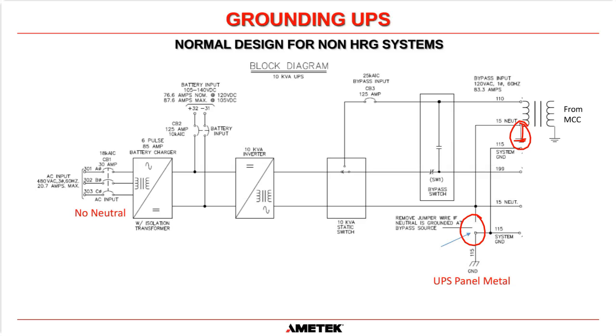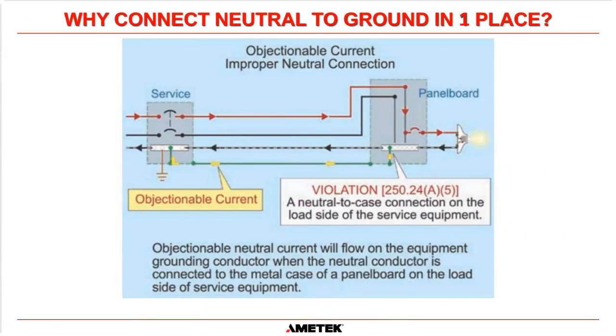Okay, so we're still connecting the system ground to the panel of the UPS, but the neutral bar itself is not connected to that ground. So we're not creating two points where the neutral has been connected to ground, and we'll explain why you don't want to do that. It's a violation to connect neutral to ground at 2 points. Okay, it's called objectionable current for improper neutral connection.